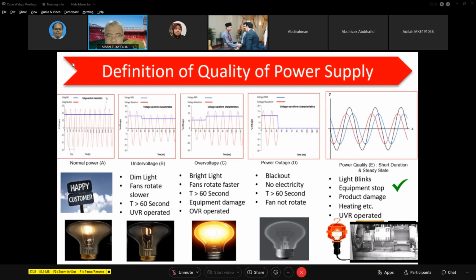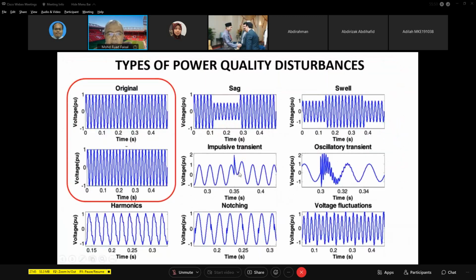So you can read it from my slide. The symptom: the light will blink. Some equipment will stop. Product will be damaged. Some product will be overheating. And UVR stands for under voltage relay operated. Okay, power quality is best understood, or maybe studied, by the waveform. As I mentioned just now, the product is the voltage waveform. The voltage waveform is a sinusoidal waveform.